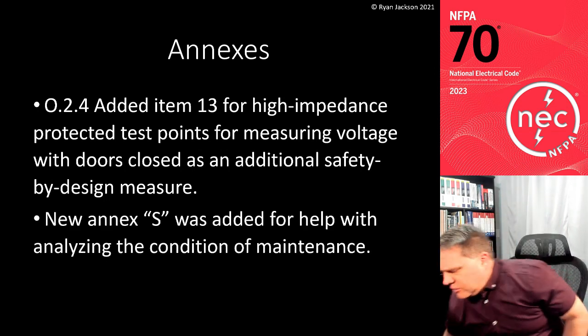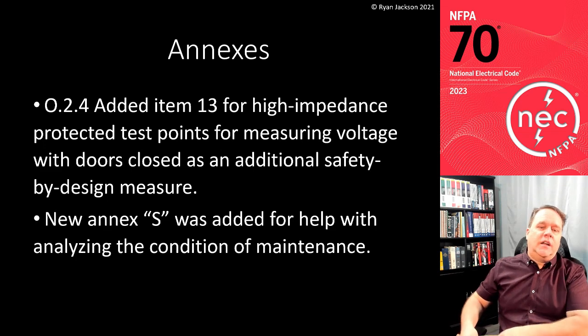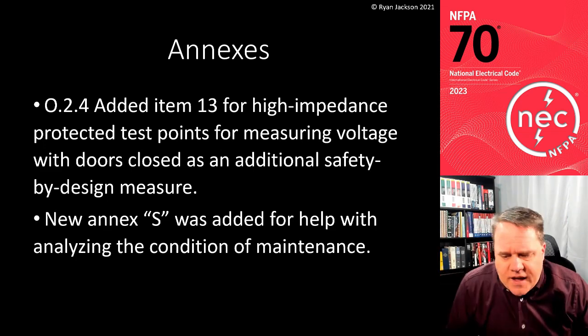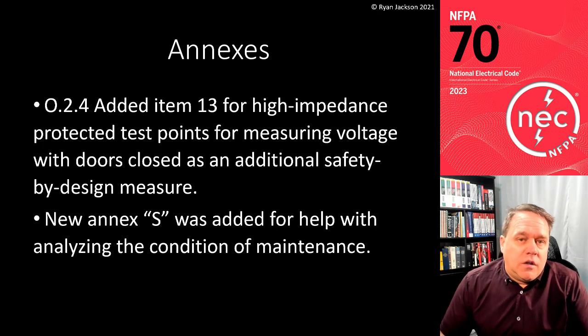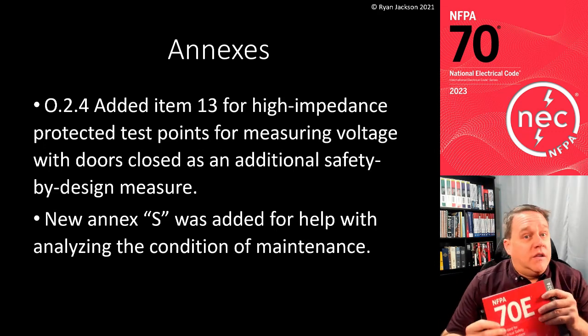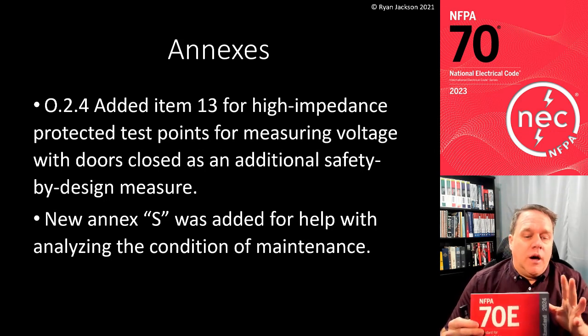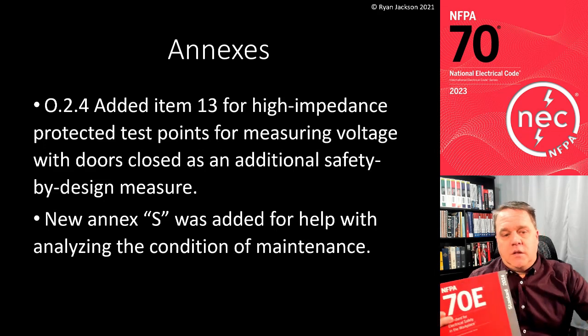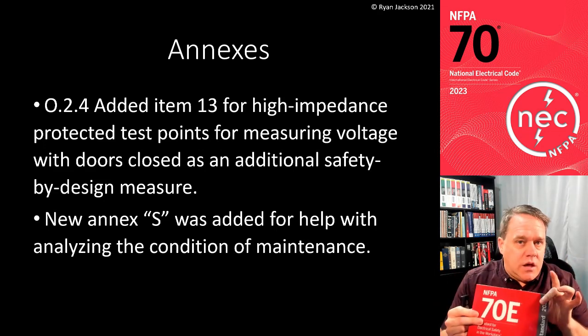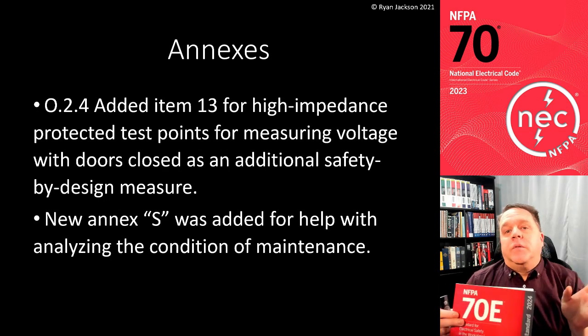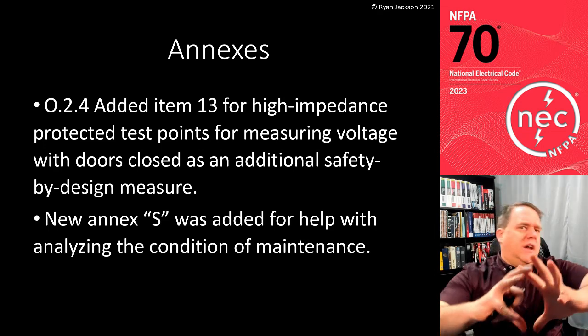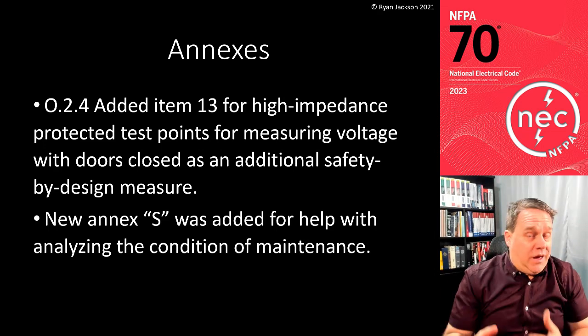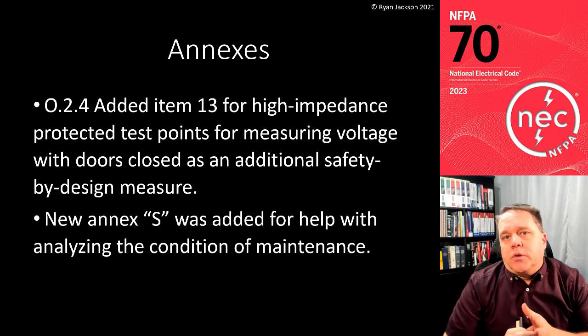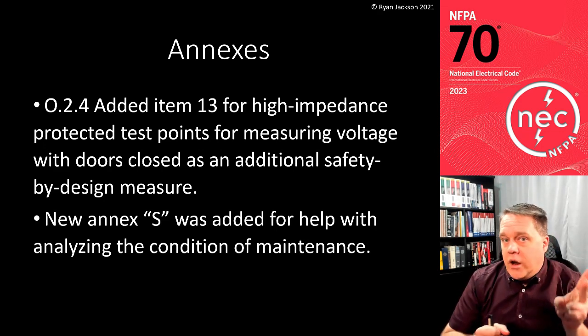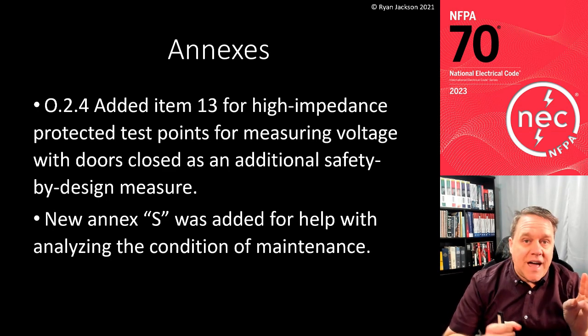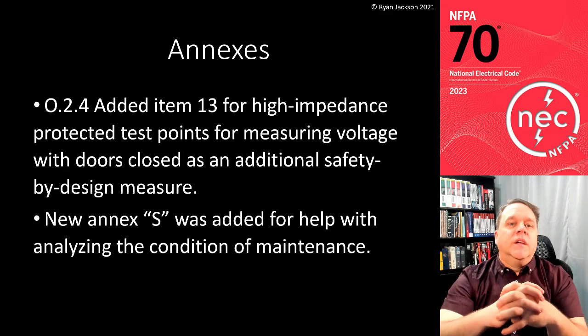The other thing that happened is we added a new Annex S for help with analyzing the conditions of maintenance. Annex S doesn't have a whole lot of information. One of the things in there is it tells you to take a look at NFPA 70B, which is the standard for maintenance. So NFPA 70, the National Electrical Code, NFPA 70E for safety-related work practices, and NFPA 70B for maintenance. A lot of people view that as kind of the trifecta for electrical equipment, and I'm one of them. I agree with that. You should have all three of those documents, and you should understand them. How do you install it? How do you maintain it? How do you work on it safely? So Annex S kind of brings NFPA 70B into the mix.